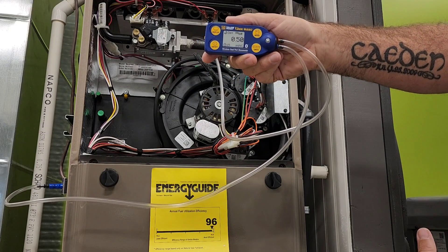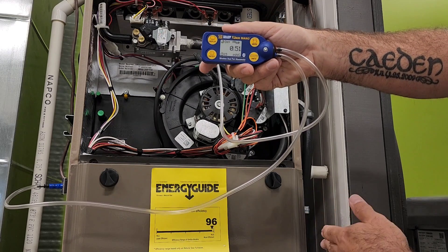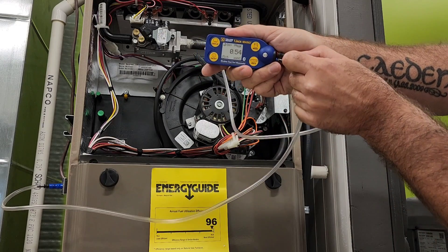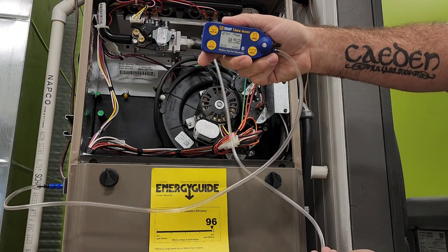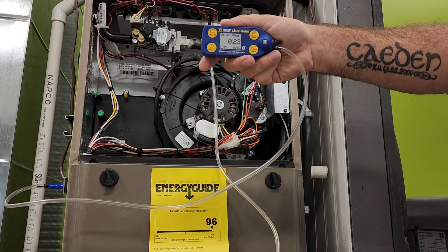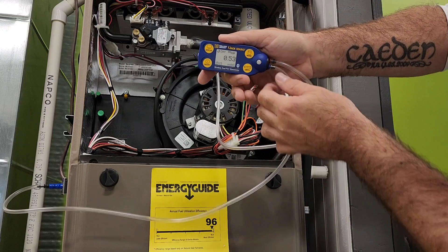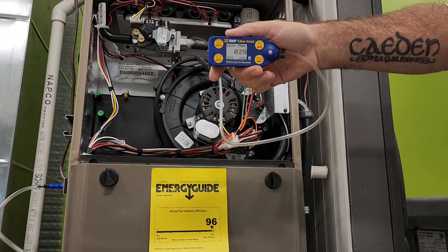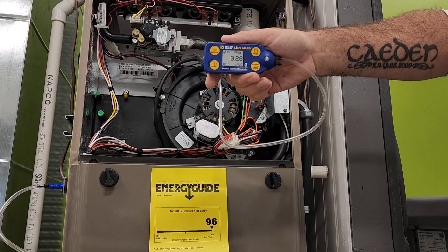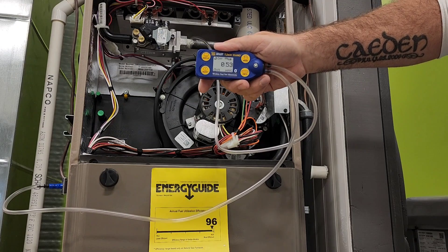At the moment we're currently hovering around what the nameplate is asking for for external static pressure of this machine. We have our total external static pressure displayed here on the screen. If we want to see independent return and supply readings we can do that just by removing a tube. Removing the supply side tubing gives a return reading of 0.23 inches water column; removing the return tubing gives a supply reading of 0.29 inches water column. Reapplying the tubing gives us our total external static pressure once again.